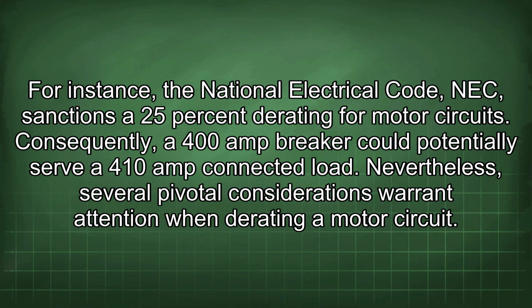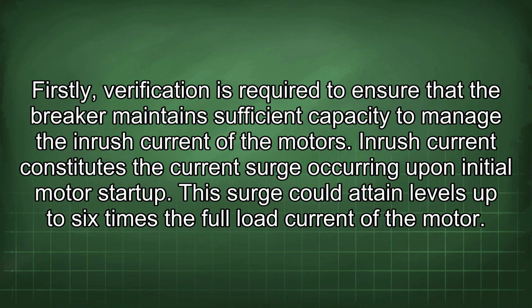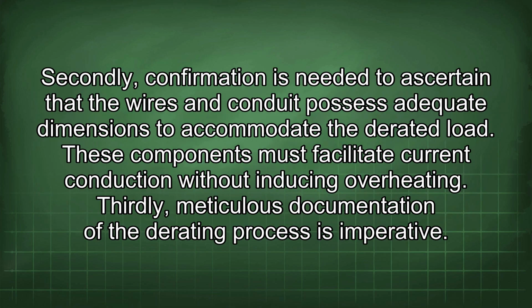Nevertheless, several pivotal considerations warrant attention when derating a motor circuit. Firstly, verification is required to ensure that the breaker maintains sufficient capacity to manage the inrush current of the motors. Inrush current constitutes the current surge occurring upon initial motor startup. This surge could attain levels up to 6 times the full load current of the motor. Secondly, confirmation is needed to ascertain that the wires and conduit possess adequate dimensions to accommodate the derated load. These components must facilitate current conduction without inducing overheating.